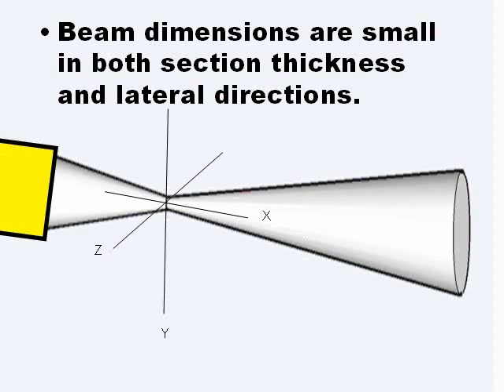Another assumption is that the dimensions of the beam are only two, not three. In reality, the ultrasound beam has three dimensions: axial resolution, lateral resolution, and elevational resolution. Elevational resolution is a dimension not shown in the picture, but it does produce artifacts.